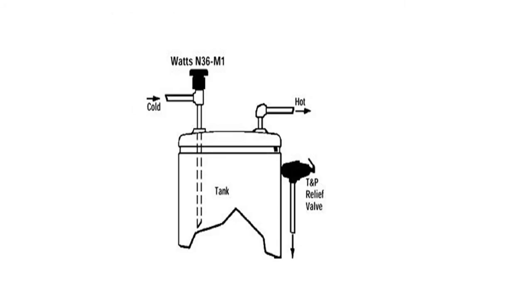A vacuum relief valve is a simple device that prevents collapse of a water heater or storage tank. It is required on bottom-feed water heaters or top-feed water heaters without a dip tube that has an anti-siphon hole in it — a little hole that's actually drilled into the top of the dip tube going into the water heater. If the building's water line were to shut down, the system can back-siphon the cold water line.